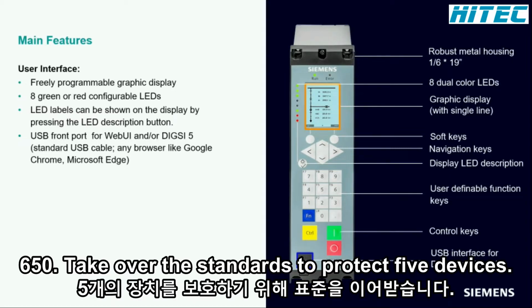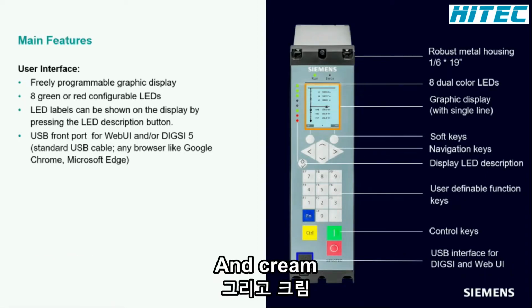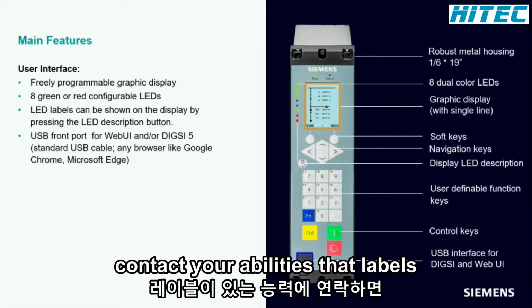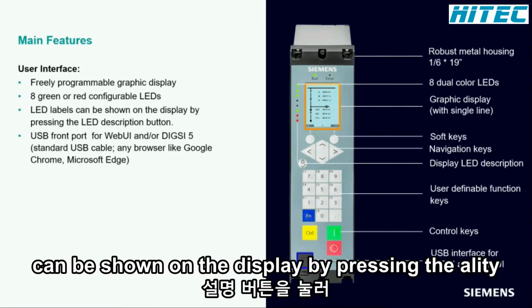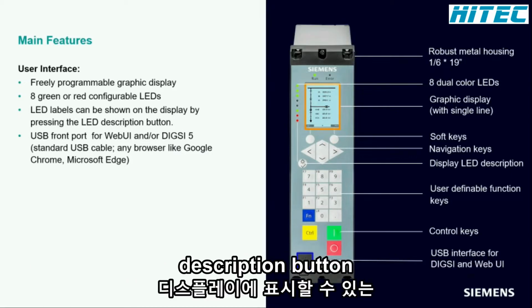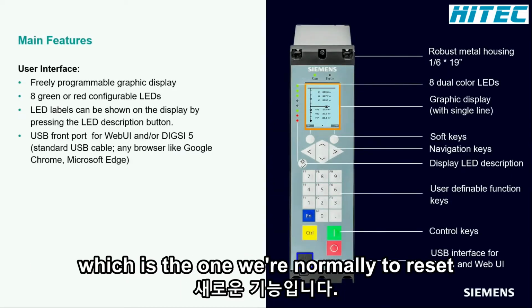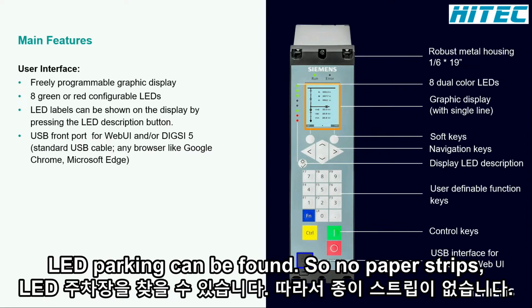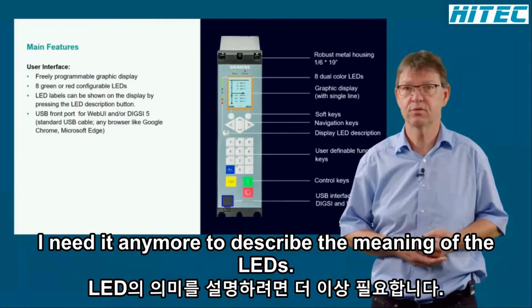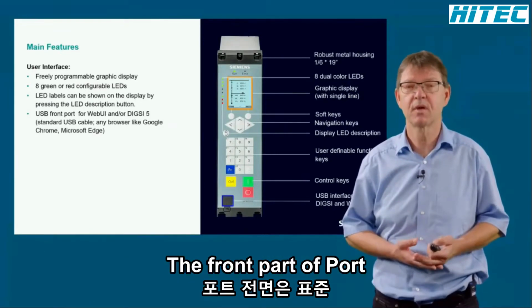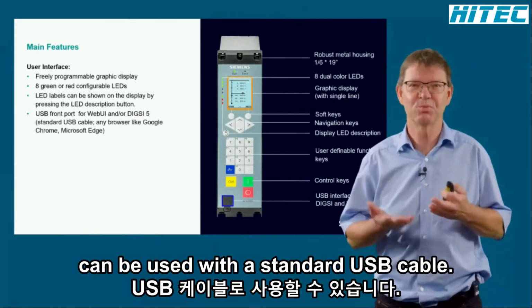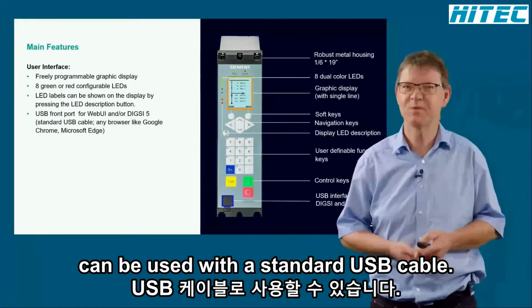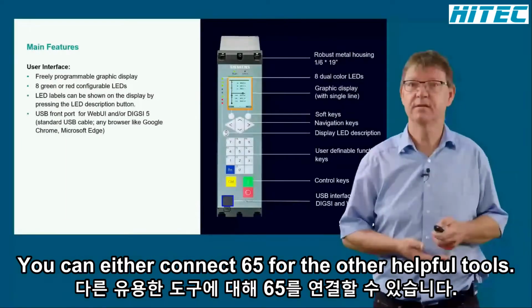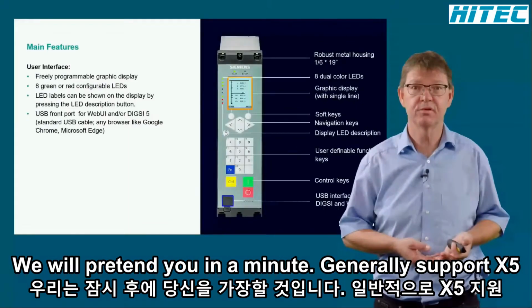The graphic display is freely programmable, and its resolution is identical with the standard SIPROTEC 5 devices. There are 8 red and green configurable LEDs. Their labels, and this is a new function, can be shown on the display by pressing the LED description button, which is the one where normally the reset LED button can be found. So no paper strips are needed anymore to describe the meaning of the LEDs. The front port can be used with a standard USB cable, where you can either connect DIGSI 5 or the other helpful tools we will present to you in a minute.